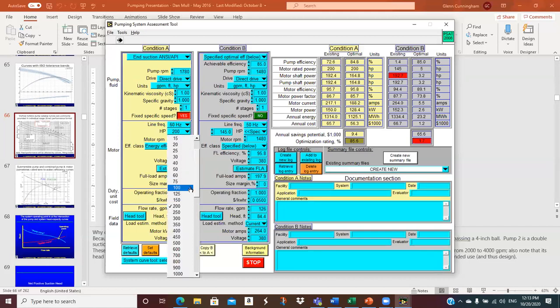And then horsepower, you've got all kinds of different horsepower. You can specify if you have a strange situation. We can go all the way up to 50,000 if we want to. Wow, that's pretty significant. Motor RPM, it could be different than the pump. If you've got a belt-driven system, you've got a pulley ratio, so the motor could be faster or slower than the pump. Just depends on the pulley ratio.